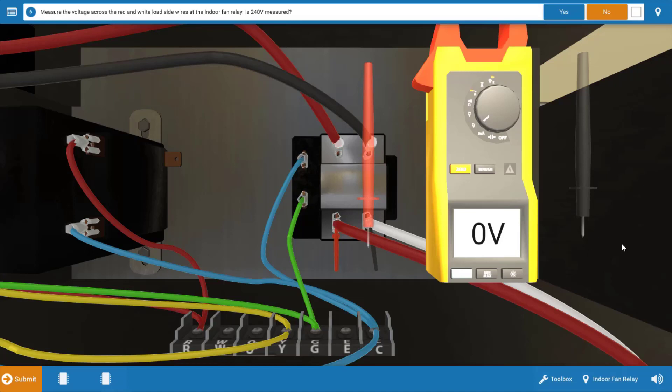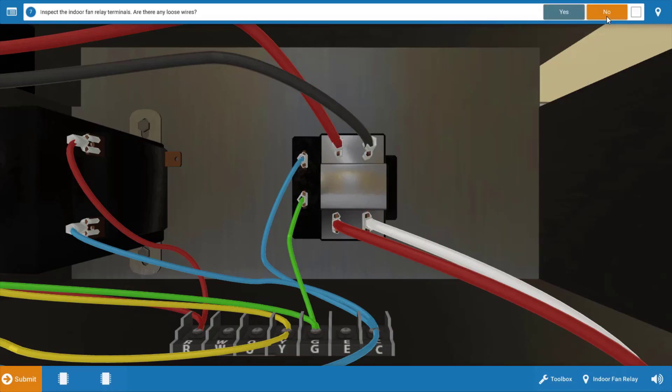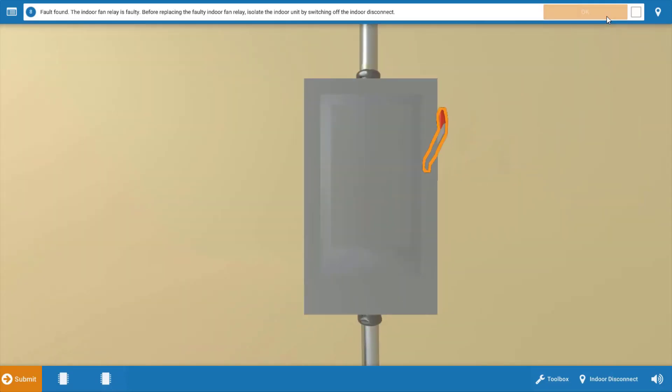Now, they shouldn't be open. We've got 24 to the coil. It should be pulling the contacts in. This most likely means the coil is probably open. So our next step is to click no on the procedure guide and inspect for any loose connections. And if we look here, it looks like all the connections are secure. So there's no loose wires. We're going to click no.